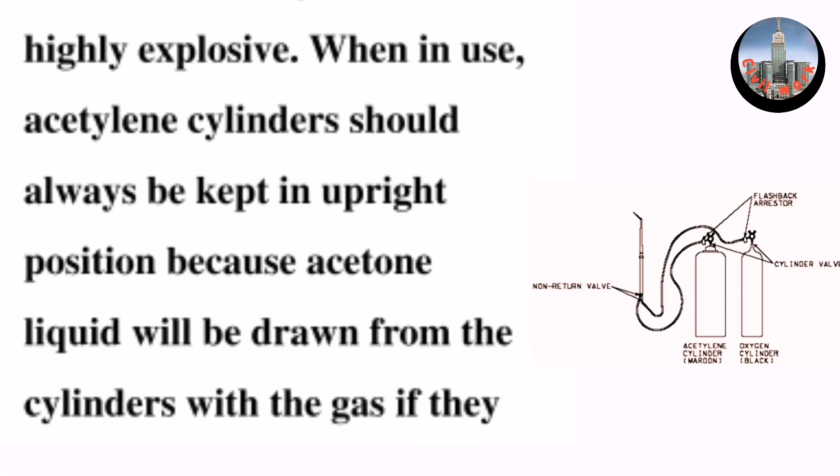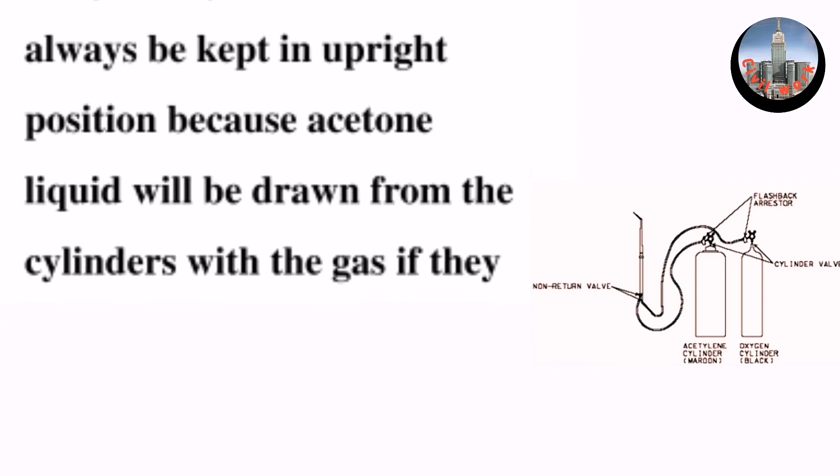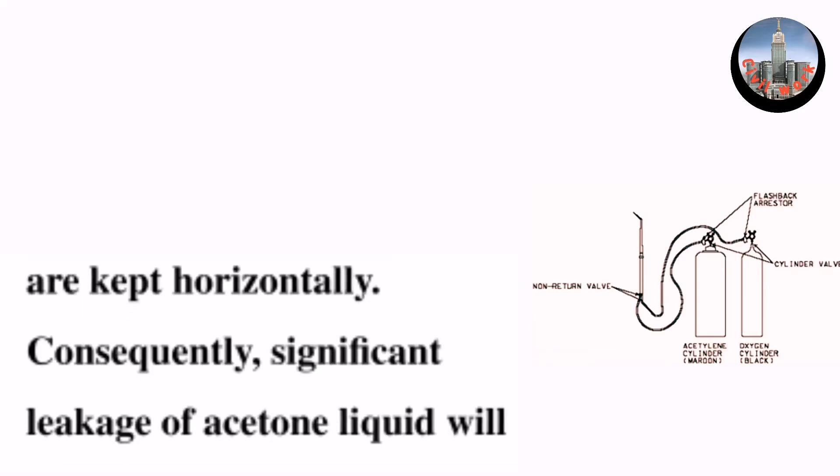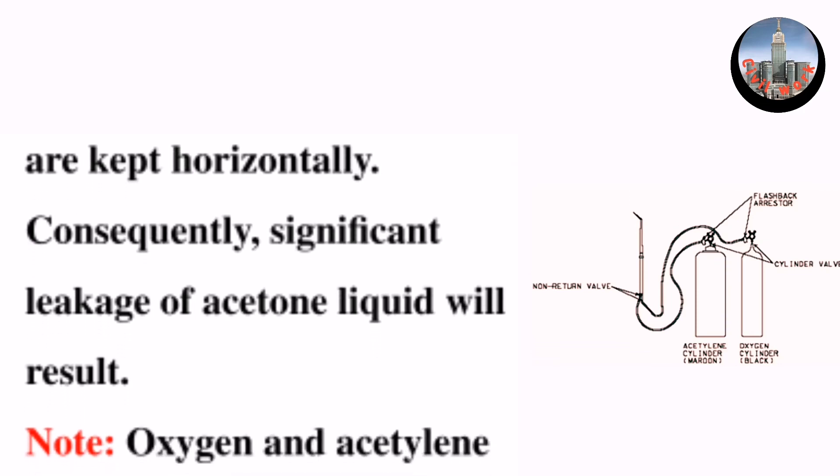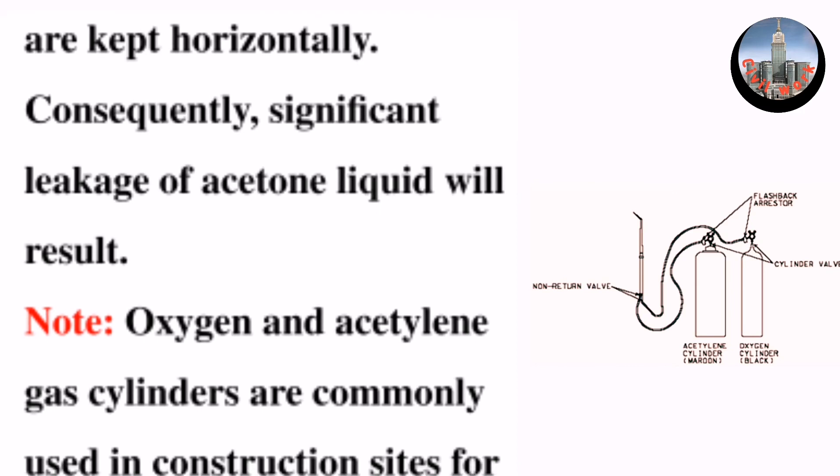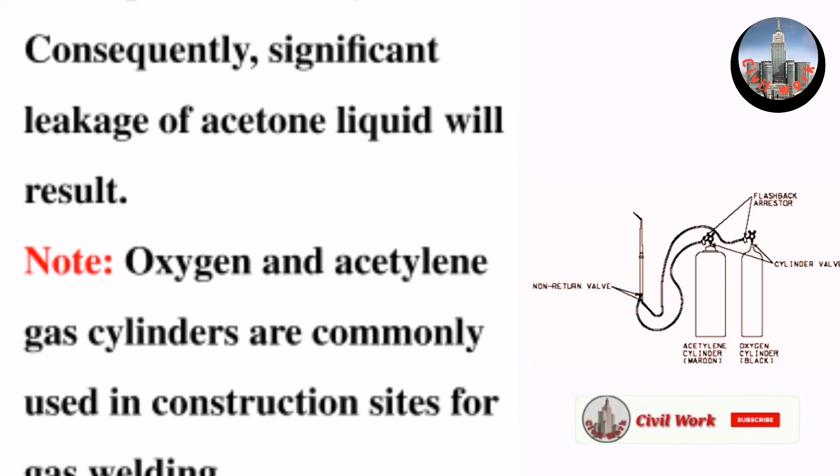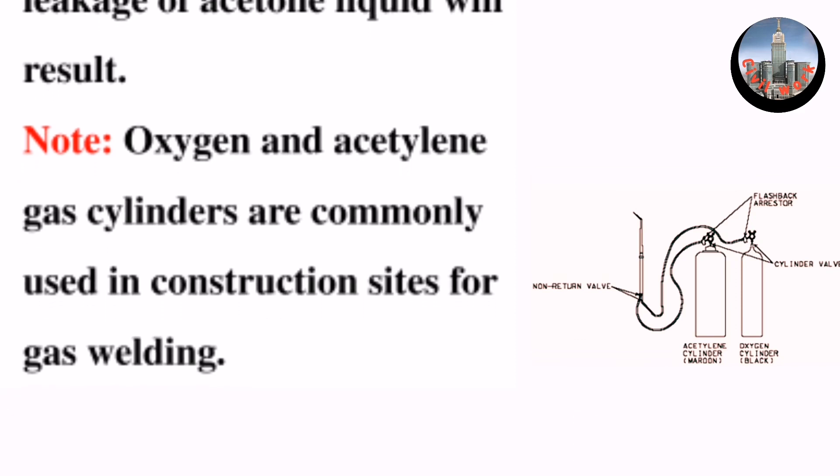Because acetone liquid will be drawn from the cylinders with the gas if they are kept horizontally. Consequently, significant leakage of acetone liquid will result. Note: oxygen and acetylene gas cylinders are commonly used in construction sites for gas welding.